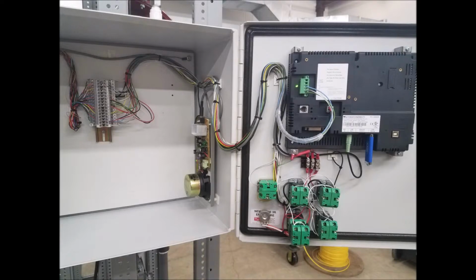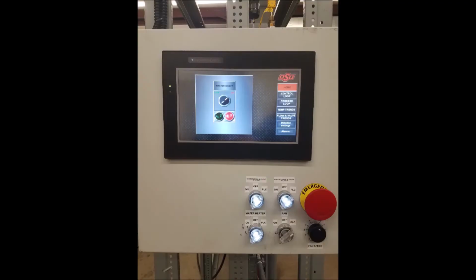Here is the view inside of our HMI panel. We added a speaker for alarms. On the outside of our HMI panel are 4 switches, which are able to turn the pumps, water heater, and radiator fan to on, off, or PLC mode. These field switches will override the PLC program if adjusted. Also shown is the e-stop, which will stop the entire process.